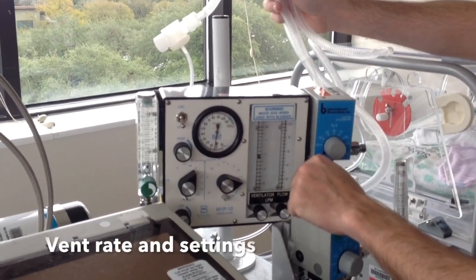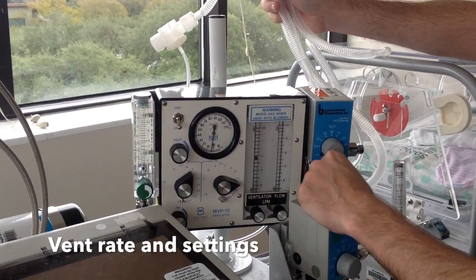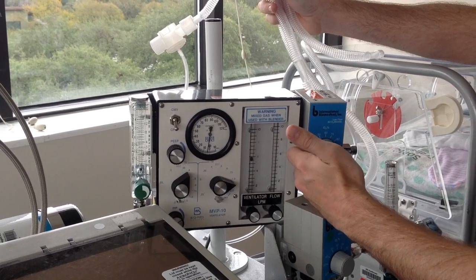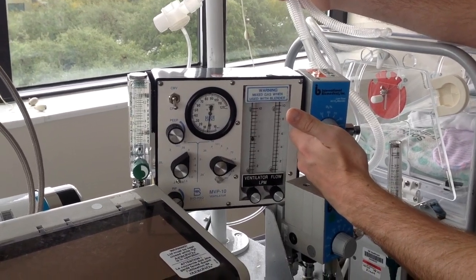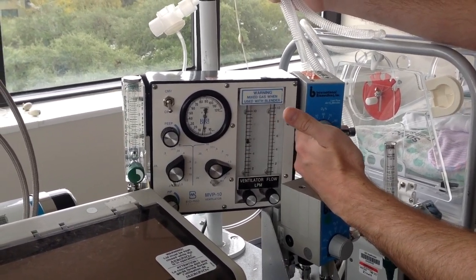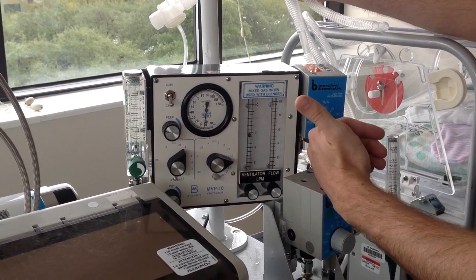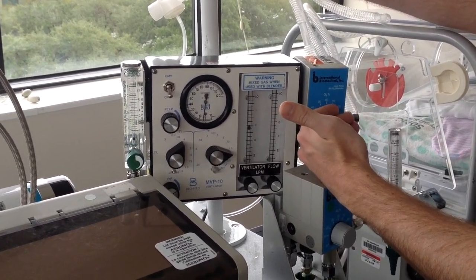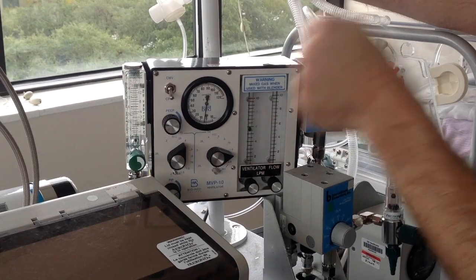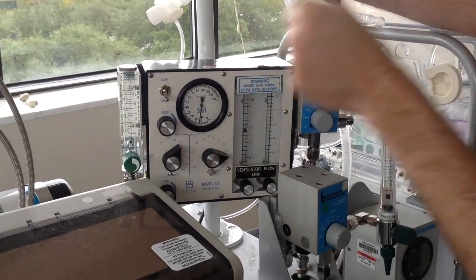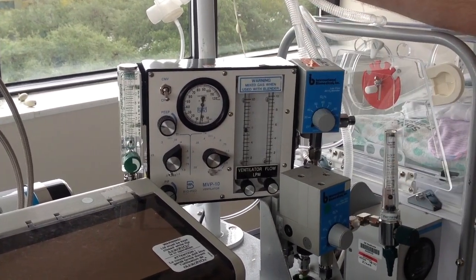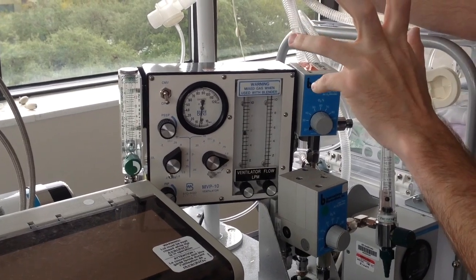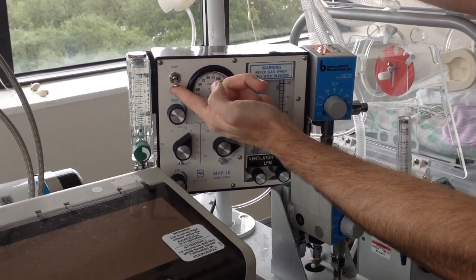Okay. So we're going to talk about your CMV, how it's labeled here, your rate, IMV. This is not SIMV, synchronized intermittent mandatory ventilation. This is more like intermittent mandatory ventilation. There's no way to synchronize with this ventilator, so it's just going to be giving the breath at a certain inspiratory time, giving yourself a certain expiratory time, giving yourself a total rate over a minute.